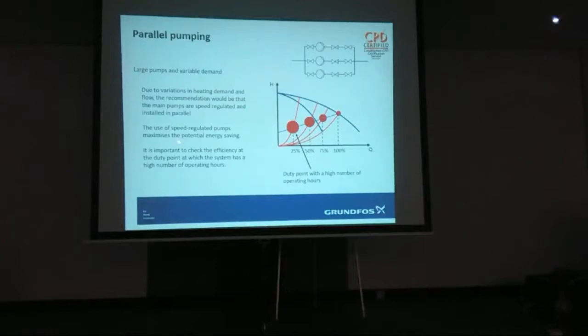Again, variable speed control, so all pumps are being used. This is shown measuring out in the station, out in the system. So one pump comes on, speeds up. When we get up to this area here, we'd start the second pump, so you have multiple pumps running at lower than 100%. Because one pump running flat out is usually more expensive than two pumps running at part load, at certain parts of the pump performance curve. Okay? And this is also important for another reason, which I'll come on to in a minute.